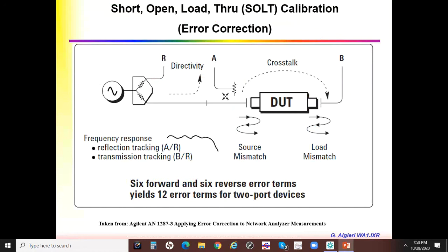So then when you do a measurement, it takes the measured value and knows what frequency it's at and so forth, and it goes and looks up those error numbers, and it corrects the measurement that you're taking by the error numbers because it knows how much the error there is. And then what it displays to you is the corrected number where they've taken out the error in the measurement device, and it gives you the actual, as true as can be, measurement of what you're looking at, either port 1 or port 2 of the device under test.